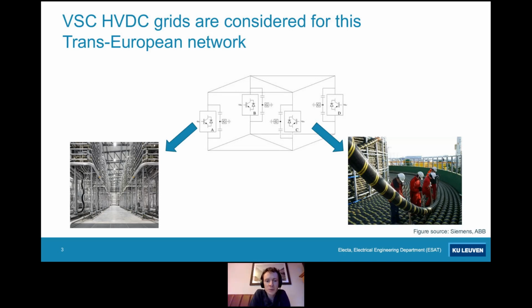For this DC technology, we have to use voltage source converters to transform the AC into DC. And these voltage source converters work on a constant DC voltage. So that makes them suitable to put in parallel, so to put them into a meshed HVDC grid. Now, the voltage source converter technology exists for about 20 years, but we have seen a huge development in the past two decades. On the converter technology, the efficiency of such a switched converter has increased from 96% to about 99%, so reaching an efficiency close to that of an AC transformer. And on cable technology, currently the cables can withstand 640 kilovolts of DC voltage. So that's also suitable for transmission level. So actually we have the DC technology to efficiently transport power over large distances.